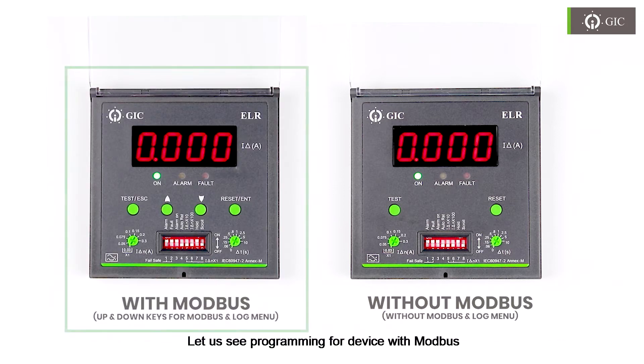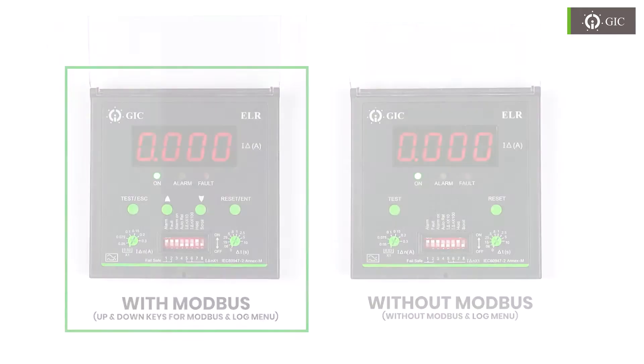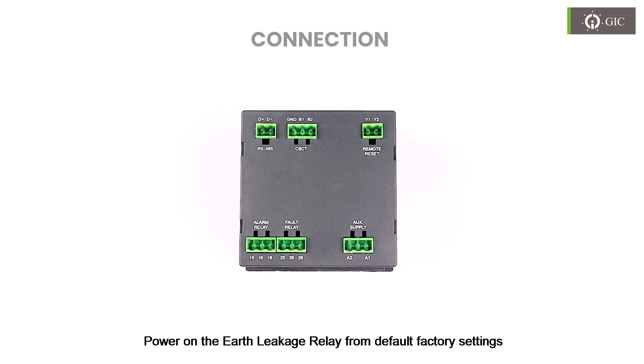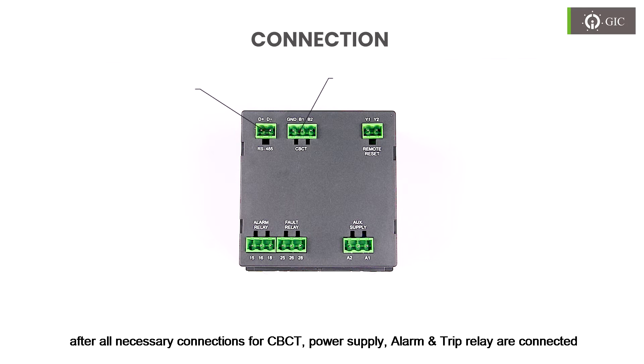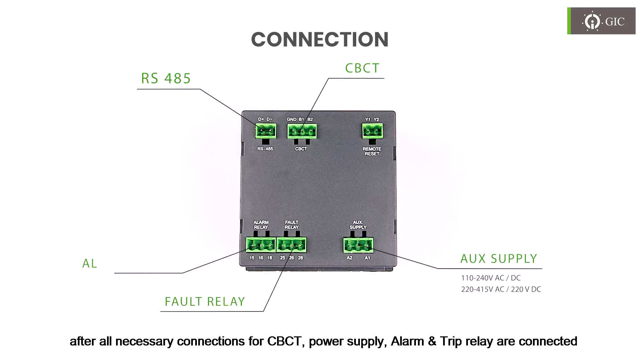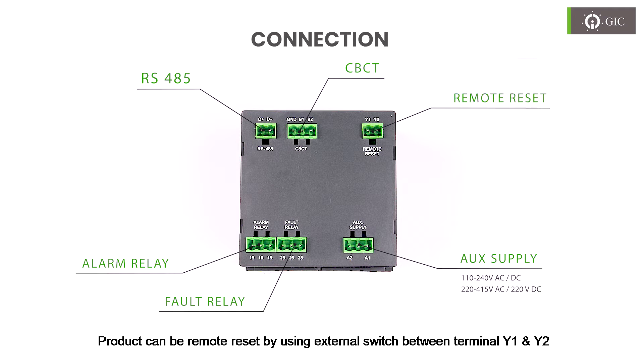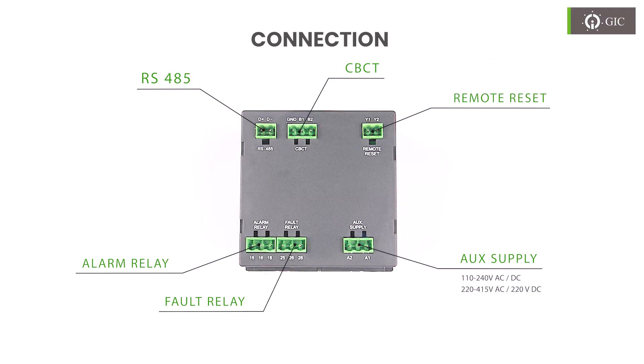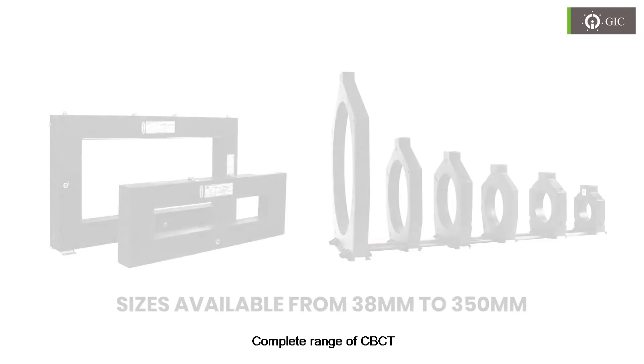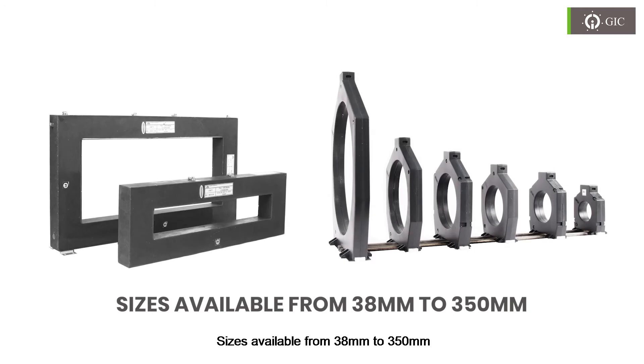Let us see programming for the device with Modbus. Power on the Earth Leakage Relay from default factory settings after all necessary connections for CBCT, power supply, alarm, and trip relay are connected. The product can be remote reset by using an external switch between terminal Y1 and Y2. Complete range of CBCT sizes available from 38mm to 350mm.